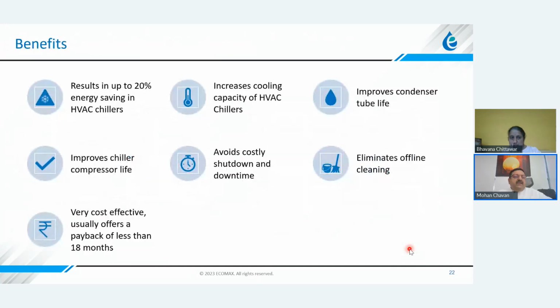When we look at the benefits that this system offers by keeping the condenser tubes clean online without any shutdown, it is up to 20% energy saving in water-cooled chillers. It will improve the cooling capacity of the chillers. It will also improve the condenser tube life, because as the tubes remain clean, there is no deposition of scales inside the tubes. That's where the corrosion is also reduced. You will also improve the life of the compressors, because the compressors will run at steady pressures. And you can avoid the costly shutdown and downtime, which is very important for buildings.